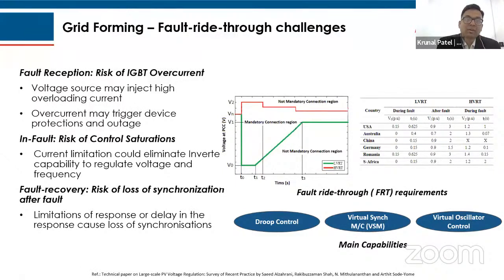Second, in a fault, there is a risk of control saturation. During a fault, whether LVRT or HVRT, the current limitation could eliminate the inverter's capability to regulate voltage and frequency. And third is fault recovery, which carries the risk of loss of synchronization after the fault. Once the fault is cleared, there should not be a loss of synchronization, because multiple grid forming inverters are connected in parallel to act as an overall microgrid, to form a grid.